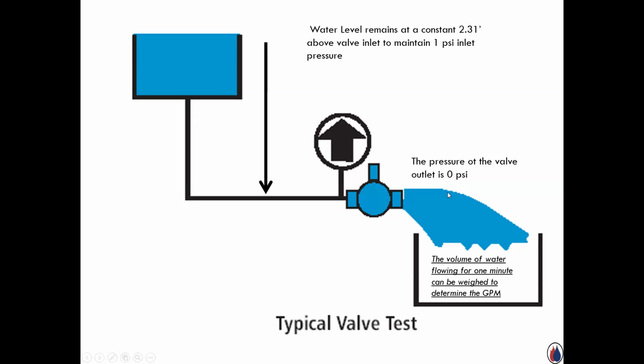And some of the reasons, and you kind of get into the weeds real quickly, and we don't want to tonight, but you can have two valves that are both, say, 2.5 inch in pipe size, but they could have internal orifices that are different. And one could be less expensive and one could be more expensive. And you start looking at the CV, and one's got a lower number, one's got a higher number. Well, the lower number is what? A lower number meaning lower GPM.